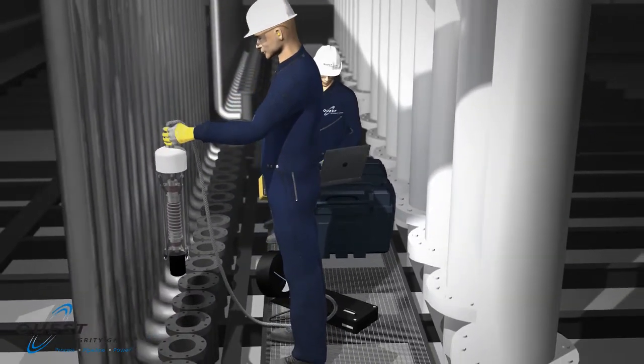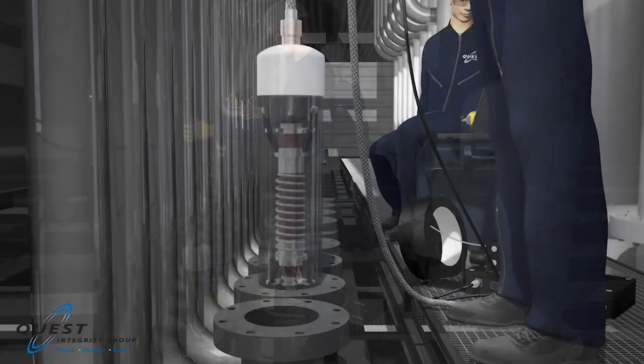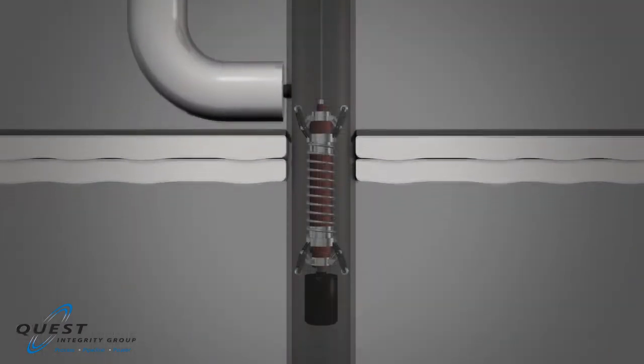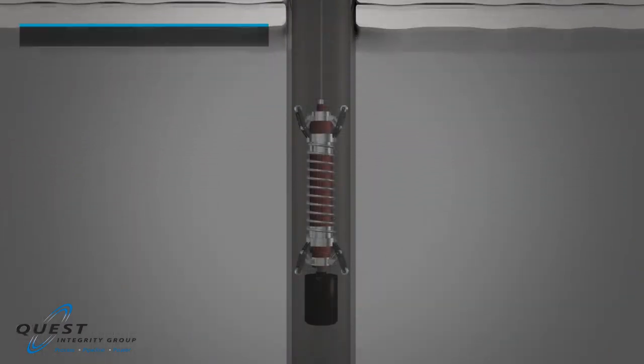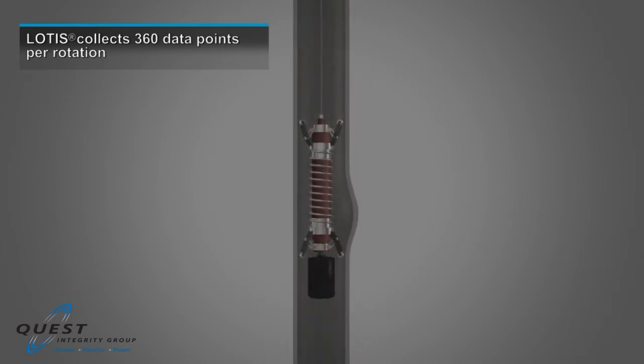The inspection starts from the top of each tube, following catalyst removal. The LOTIS laser probe is inserted into each catalyst tube and driven to the bottom. During the inspection, the probe head spins at a rate of 1800 RPM and collects 360 inspection data points per rotation.